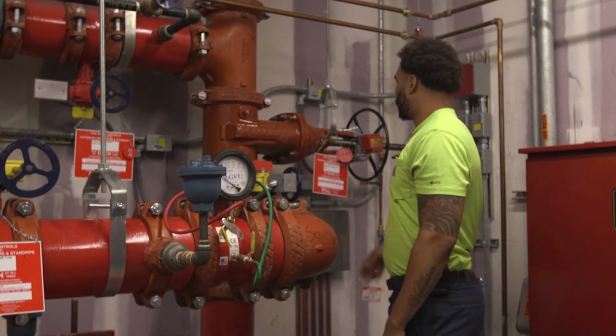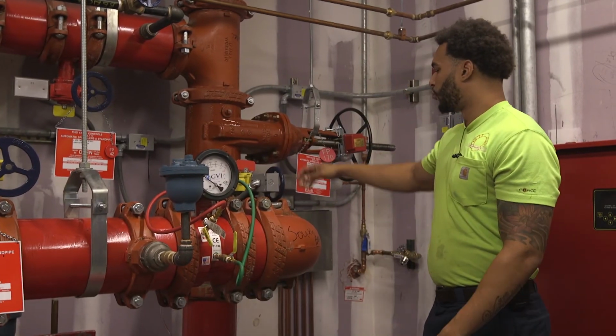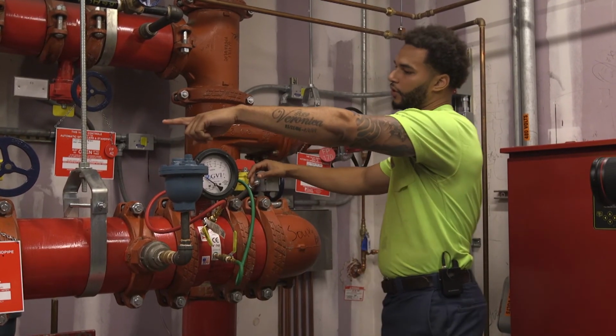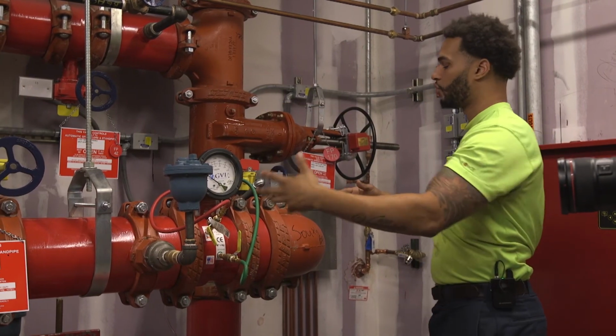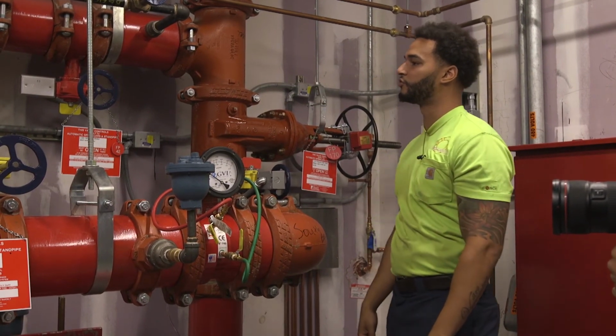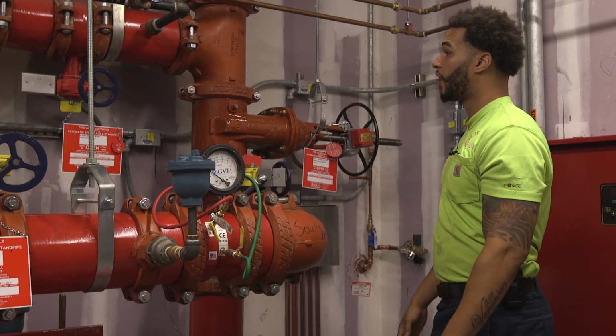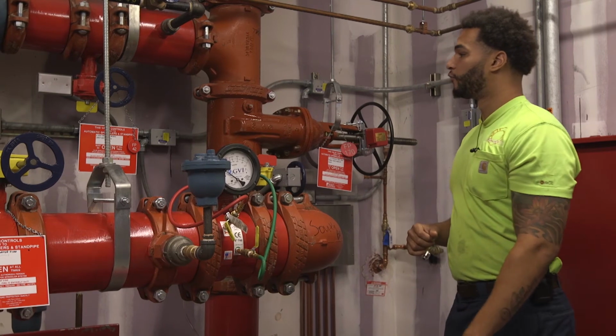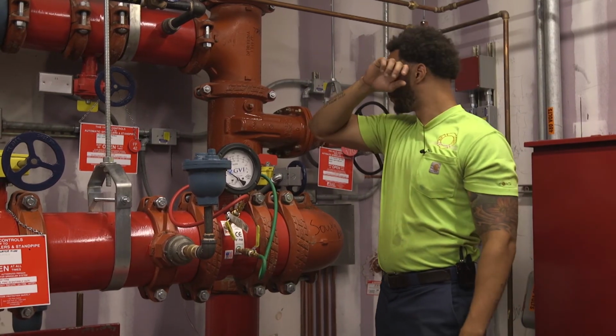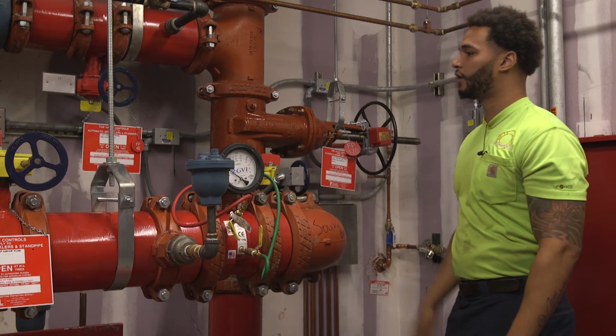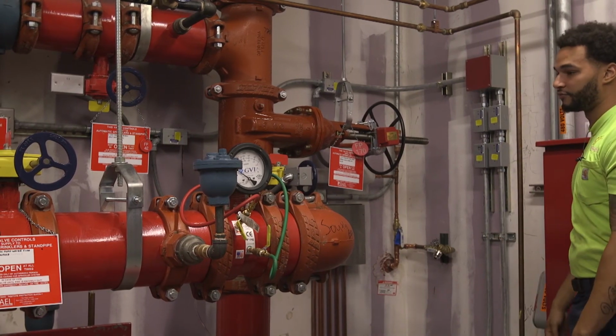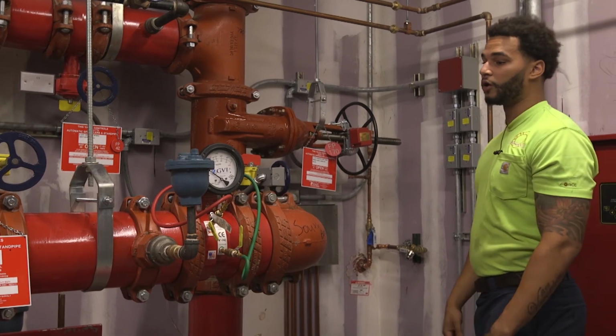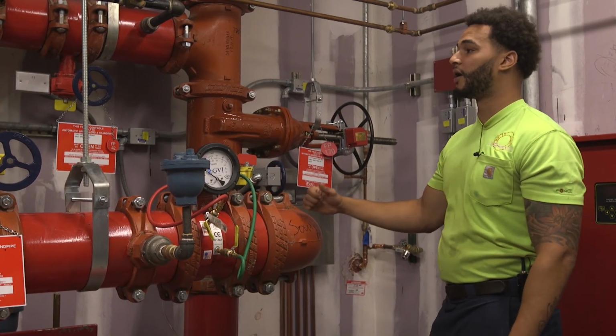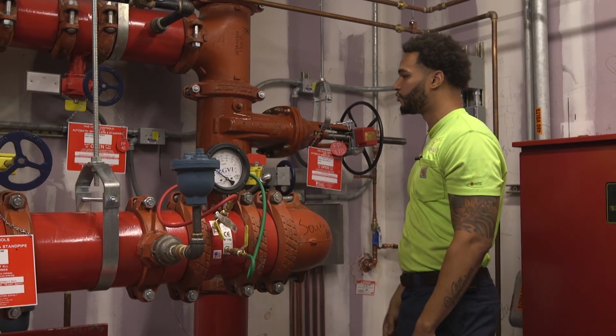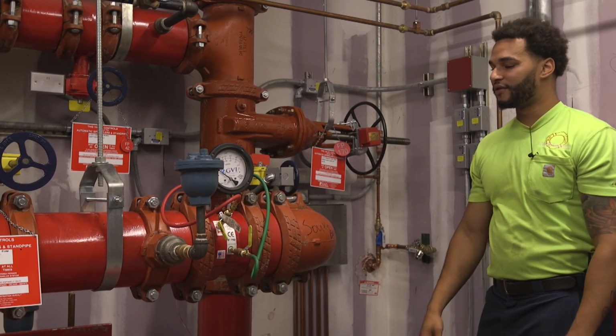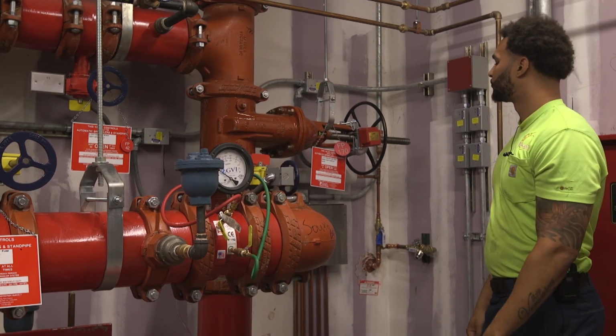All these valves are in the normally open position, except for your flow meter line here and your test header valve there. So basically where we test the fire pump, those valves are always going to be in the normally closed position always. All these valves are tampered except your two jockey pumps. Reason being, jockey pump isolation valves aren't required to be monitored, but everything else in here is monitored. If your fire pump was to kick on, it is alarmed, then you will get an alarm signal at the fire command station. If anyone wants to mess with any of these valves, you will get the alarm at the fire command station as well. Good.